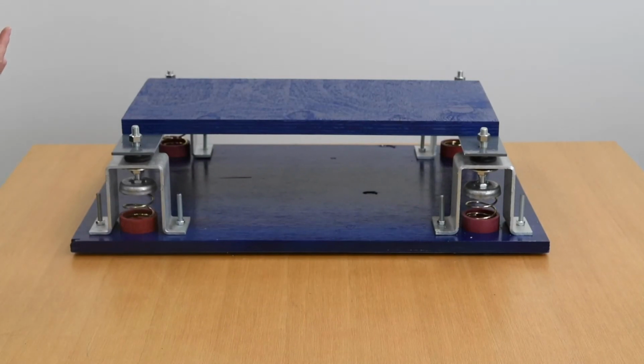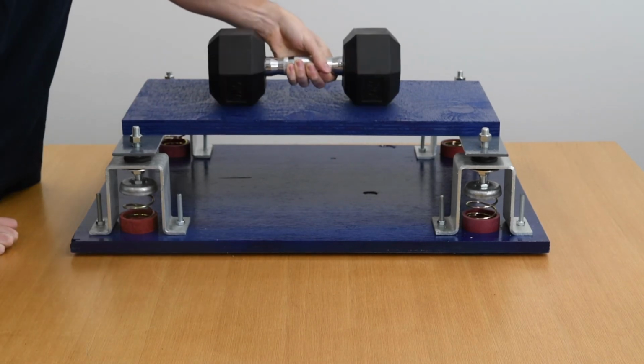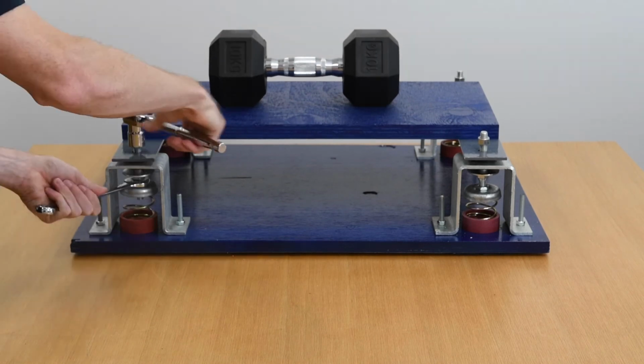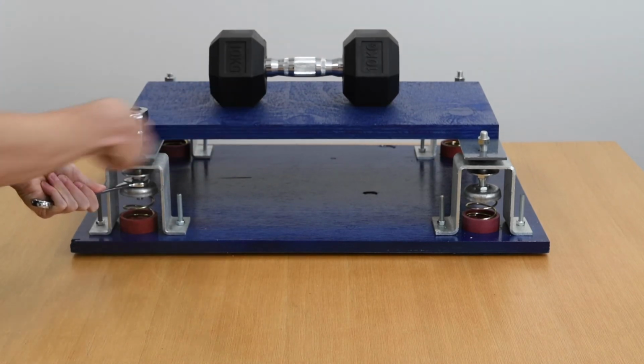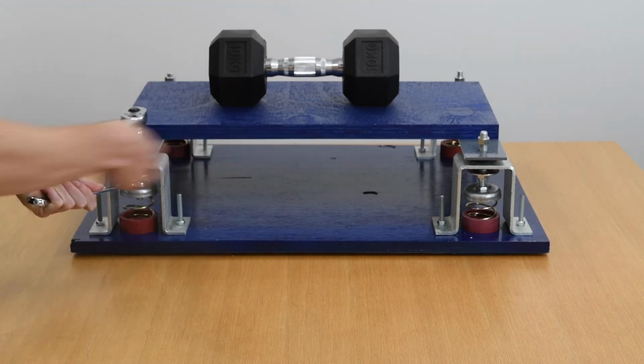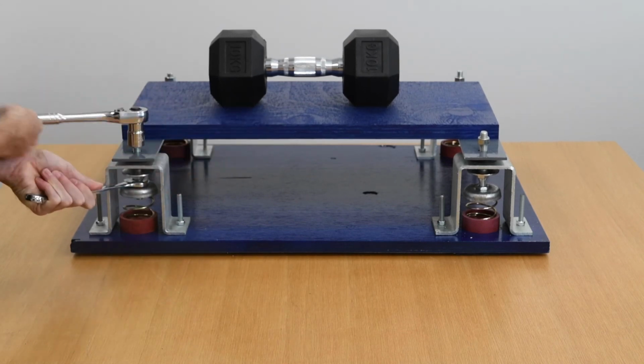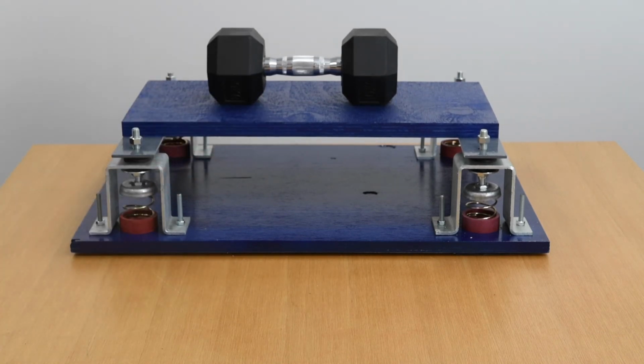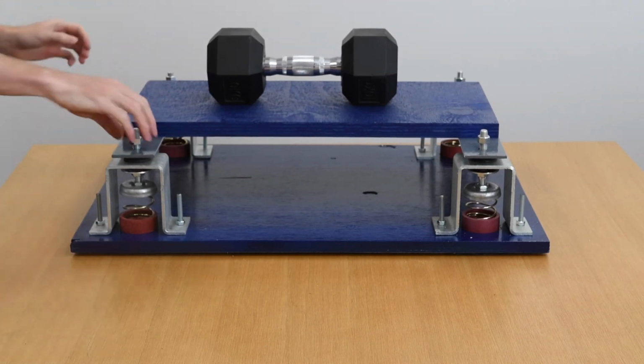Let's install this platform onto 4 mounts. If I give it a nudge, you can see that it doesn't really move and that the steel brackets are supporting the equipment. The equipment is restrained but not isolated. By turning the adjustment feature to load up the springs, we will see the platform lift off its housing. When I've done this for all 4 mounts and I give it another nudge, the platform is now oscillating as if the restraint brackets were not there at all.